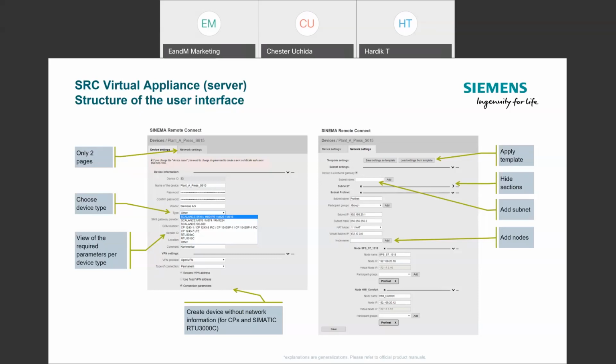You can have the same TIA Portal project with the same IP address on all your devices and just maintain one project. And with NAT, you can have multiple devices or machines with the same IP addresses, and we'll just forward it to the specific actual subnet. And then on the bottom, you can see I have a 1518 PLC and the last digit is .10. See how it created a virtual node IP address, and it's kind of grayed out. So it automatically creates this IP address for it. So when I want to talk to .10 for my 1518 PLC on, let's say, machine number 3, I'll just use this IP address, and we'll see more later on. So this is a very nice and useful feature also.